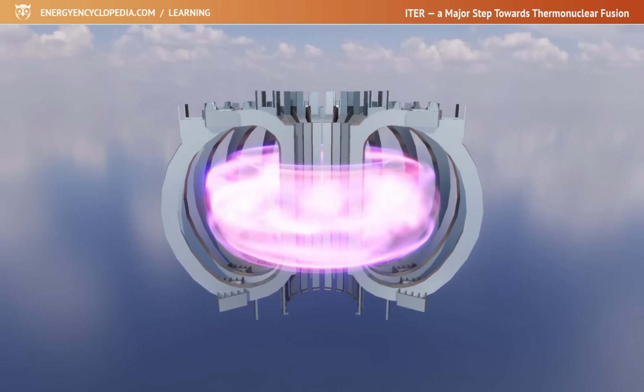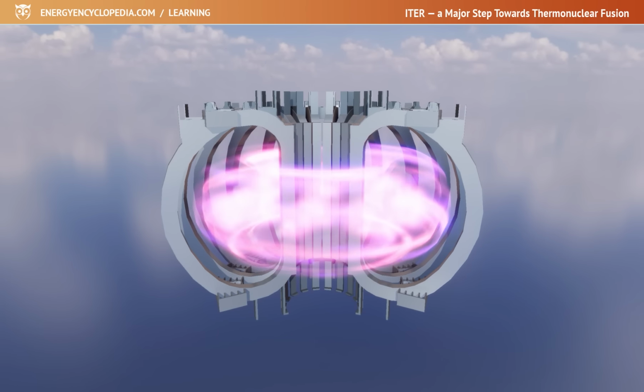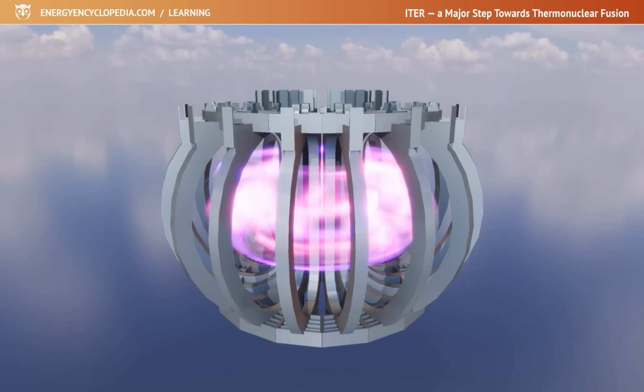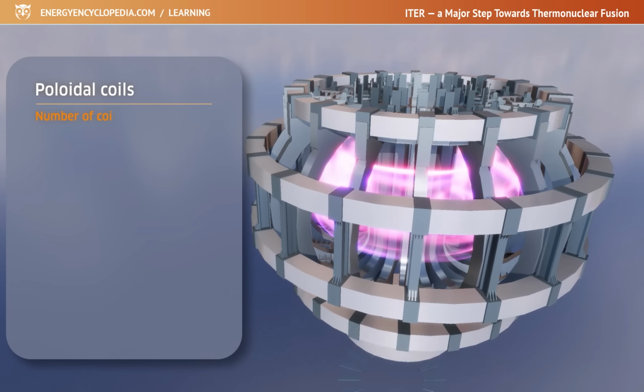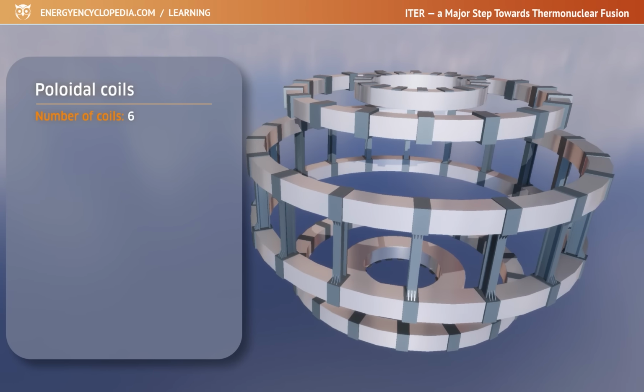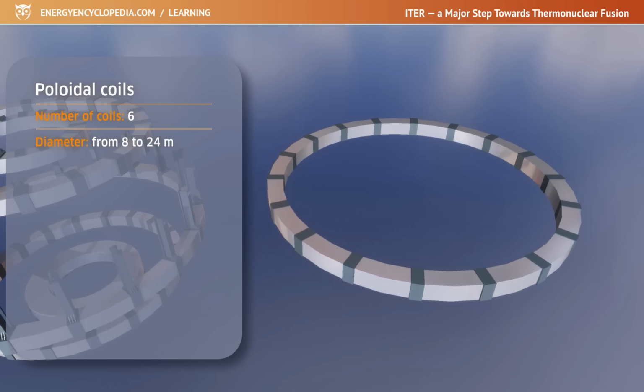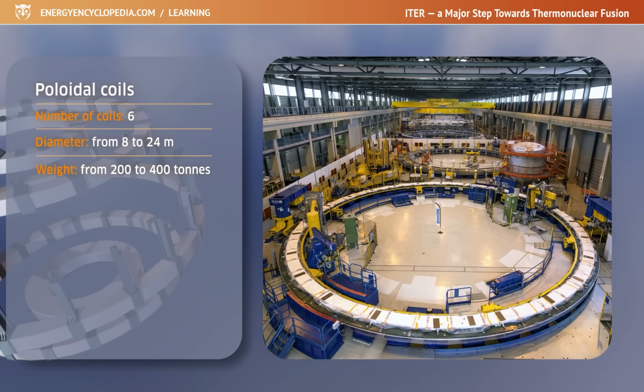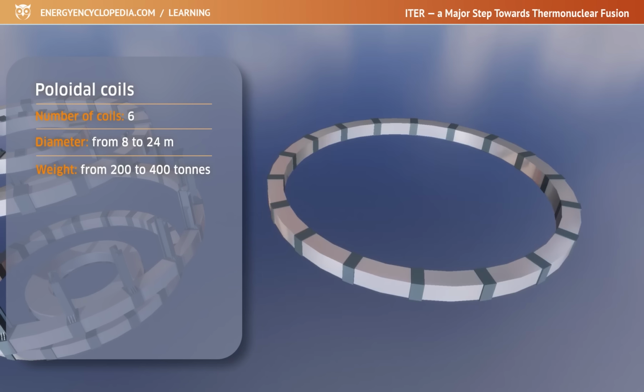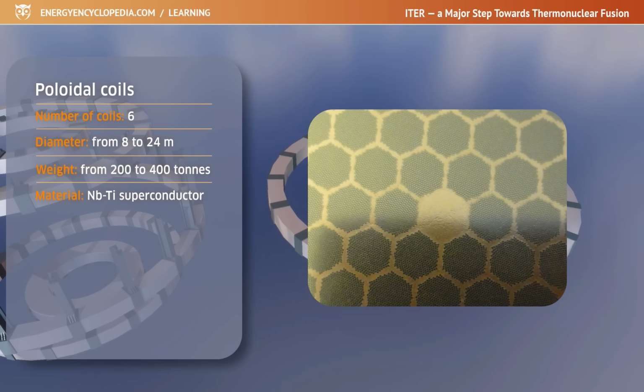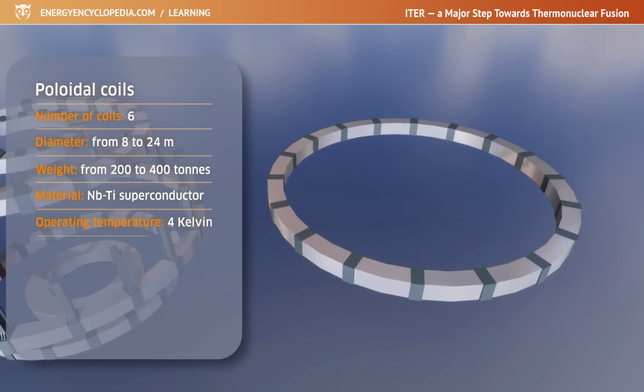Because the plasma ring tends to expand, it is held at the correct distance from the walls by a set of Poloidal coils. These are 6 giant hoops strung across the toroidal coils. The largest is 24 meters in diameter and so huge that it could not be transported. To manufacture the largest Poloidal coils, a winding facility was built on the ITER site. The coils are made of niobium titanium superconductor and cooled with liquid helium to 4 Kelvin. They are capable of delivering a magnetic energy of 4 gigajoules and creating a magnetic field of 6 Tesla.